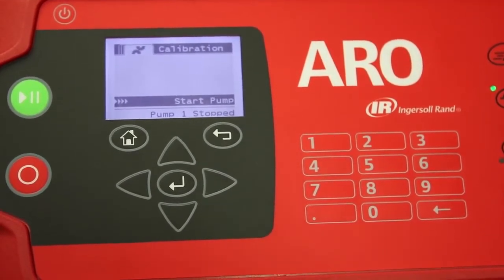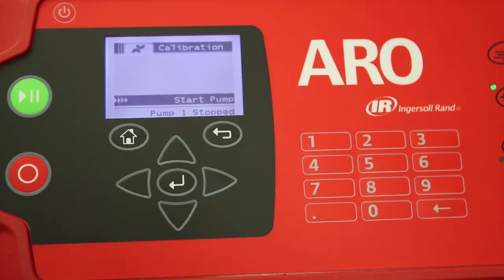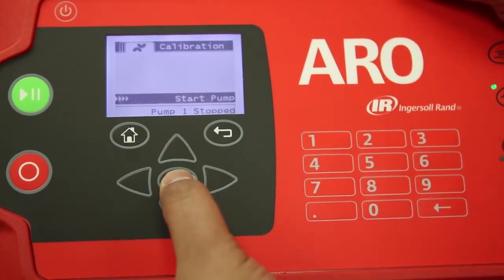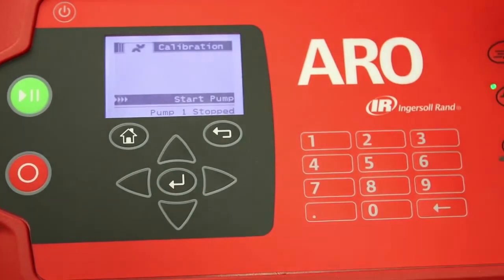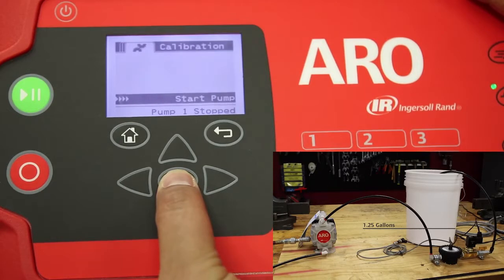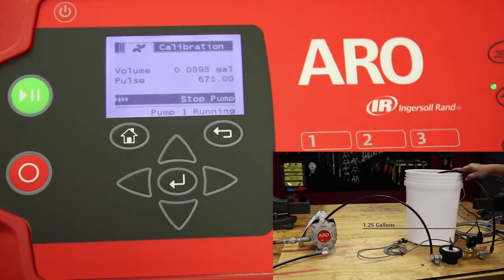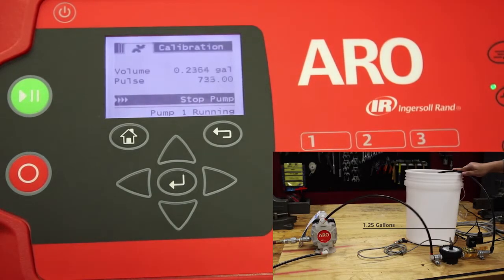pump a desired quantity of fluid into a container, preferably a calibrated container or a cylinder. Once we've pumped a desired quantity, we'd want to then come back to the controller and enter the actual quantity of fluid pumped. The controller then takes the difference, if any, and performs calculations in order to calibrate the flow meter. Let's go ahead and start the pump in order to pump the quantity of fluid. To begin, press start pump. We'll stop the pump when we hit the 1 gallon mark in the calibrated cylinder.